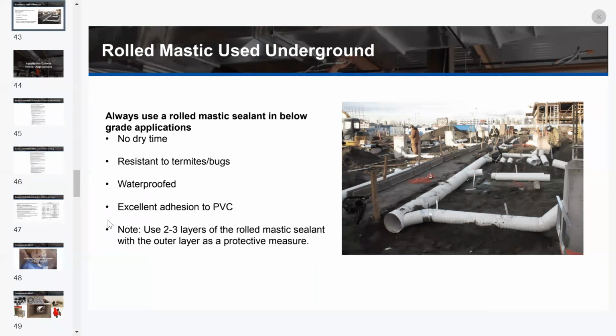It's key because you have no dry time. It's naturally resistant to termites and bugs, and it is waterproof and offers excellent adhesion to PVC. It's important, though, that you use 2 to 3 layers of the rolled mastic sealant in a subgrade. The why is the initial layer seals for your air leakage and waterproofs the joint. The second and possibly third layer is considered your protective barrier. Just make sure that you're protecting that initial layer when that area gets backfilled.